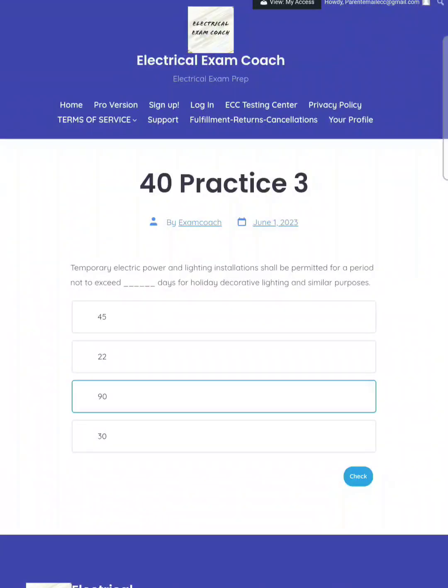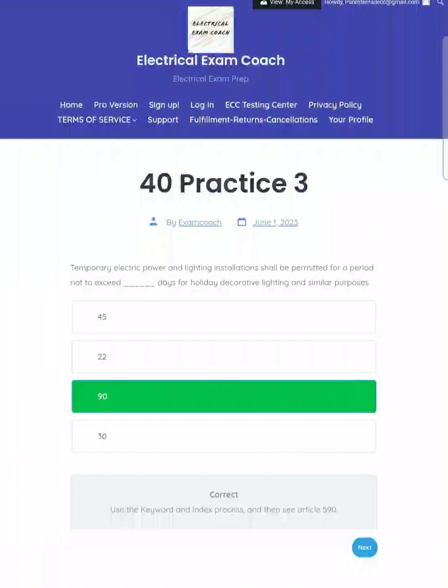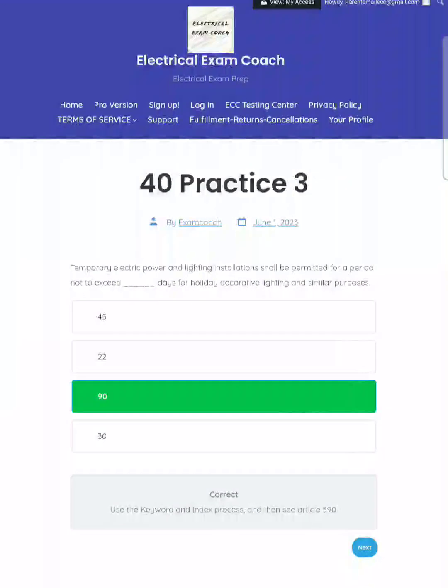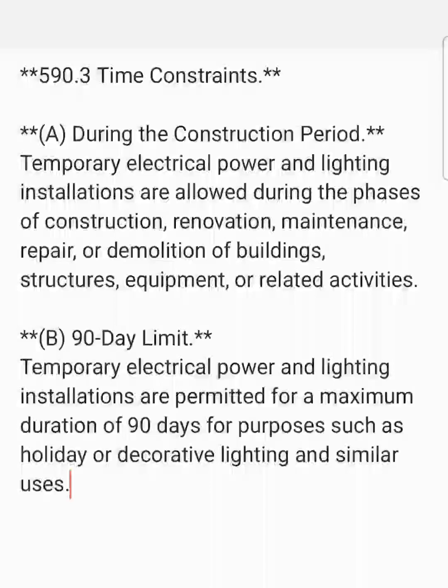The correct answer is 90 days. For this one, we're going to head to Article 590. Let's take a look at the paraphrase code language. When we get to Article 590.3, it talks about the time constraints for these temporary installations.